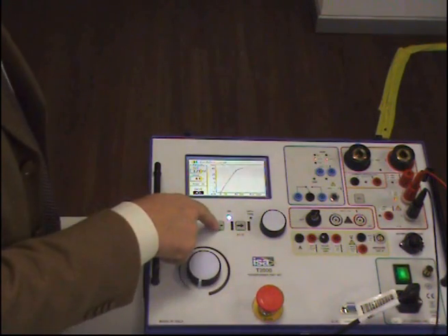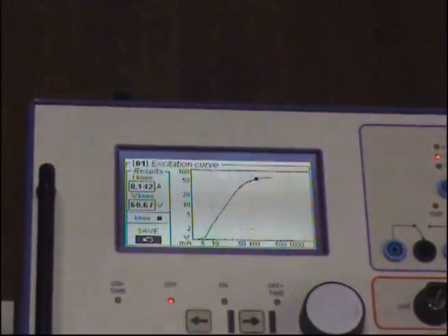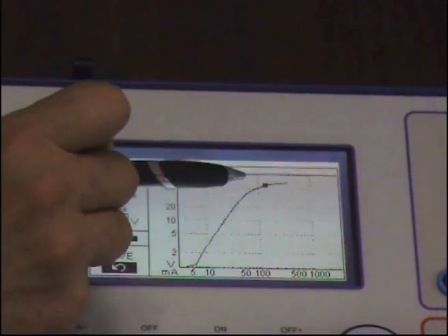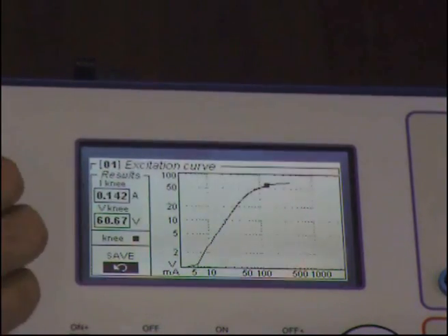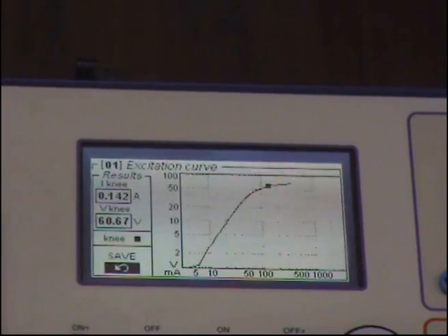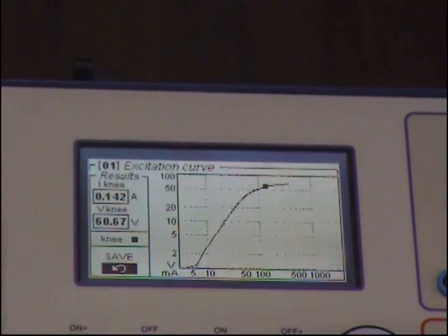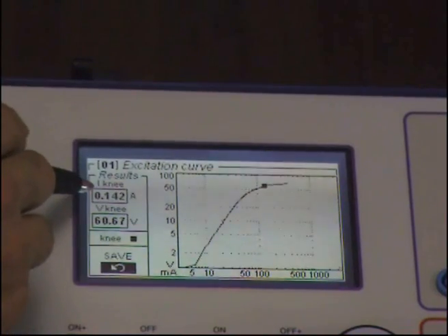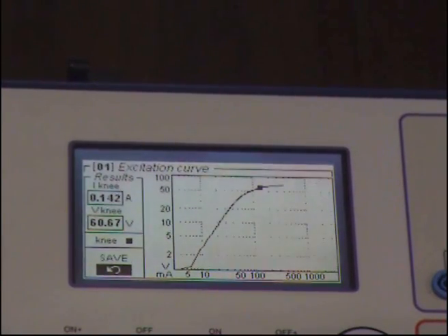Now look — as soon as I press off, I see here a black dot, and this black dot is telling me this is the knee point. The knee point has been found at 60.67 V, which is 1% different with respect to the nominal value. The current is less than expected, which means this is a good transformer.